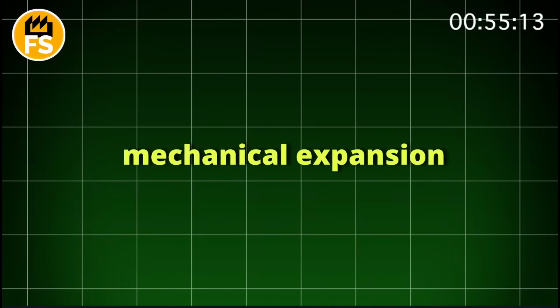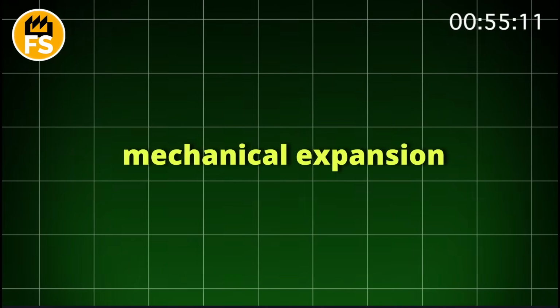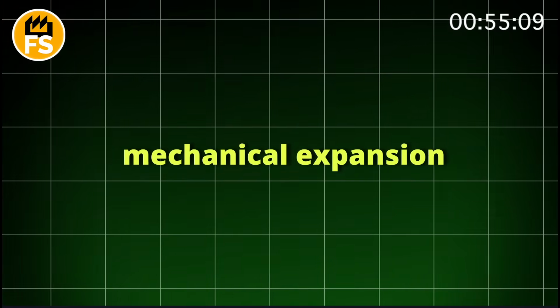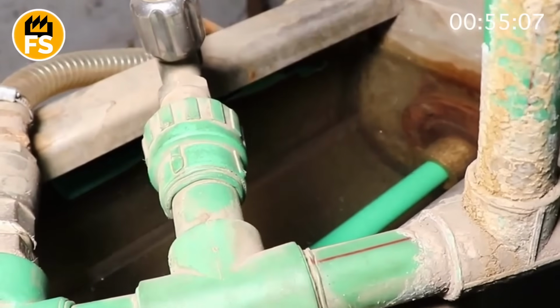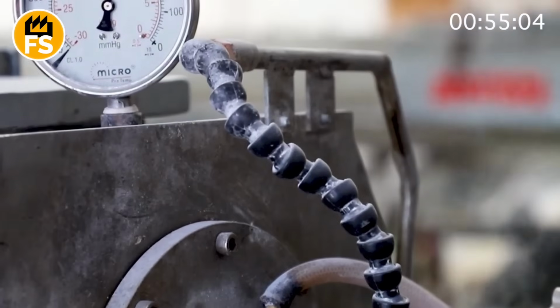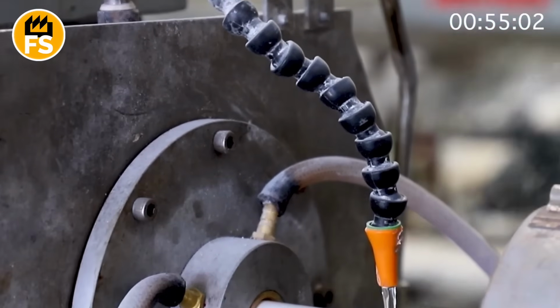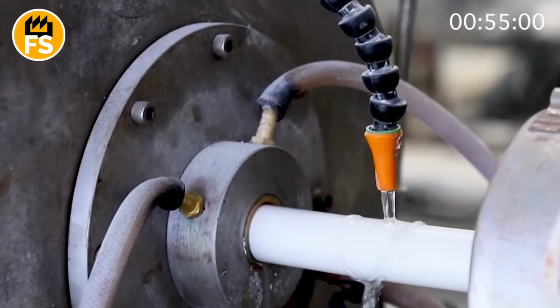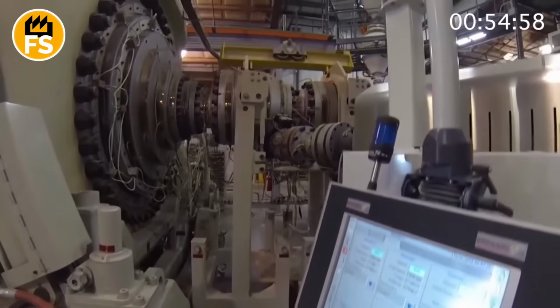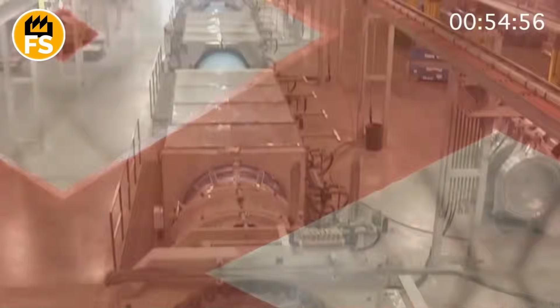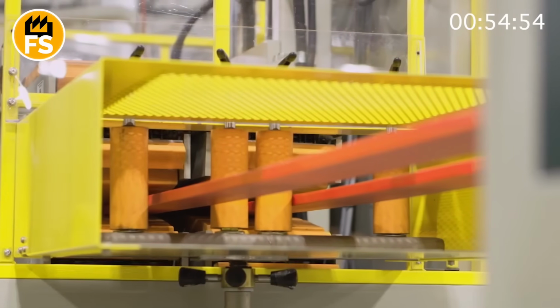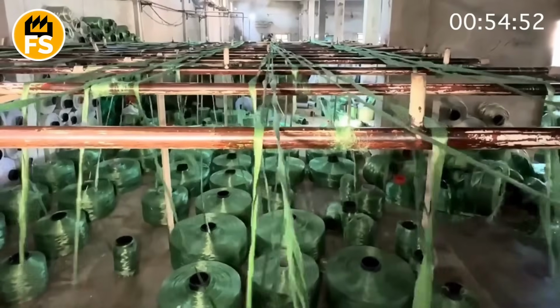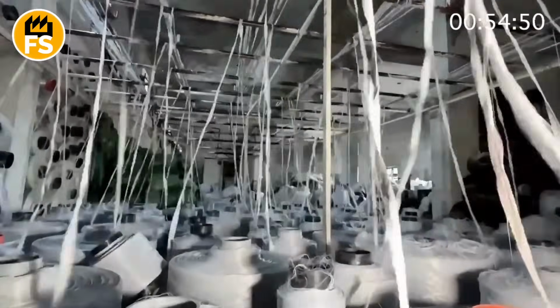After stringing, mechanical expansion begins. A unique procedure where special mandrels are inserted into the tubes, or they are pressed from the inside with hydraulics. This expands the copper, and it presses tightly against the holes in the fins. The contact must not just be tight, it must be perfectly tight, because this is the area where heat will be transferred from the hot fluid to the cooling air, or vice versa. Every microcrack is a loss of efficiency.